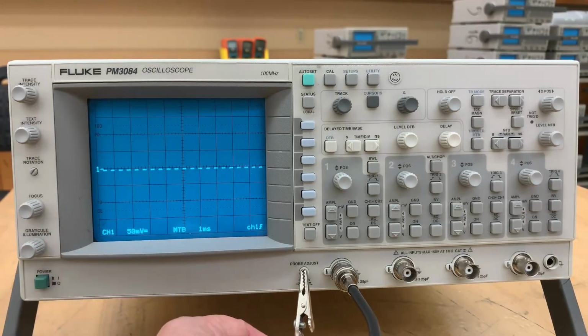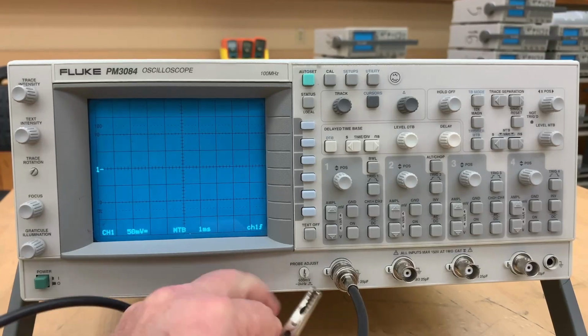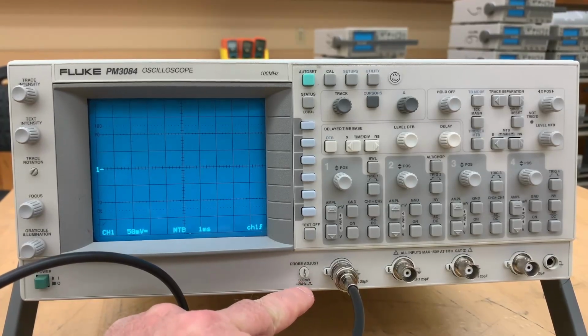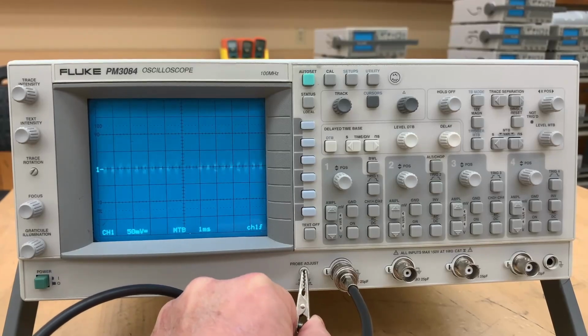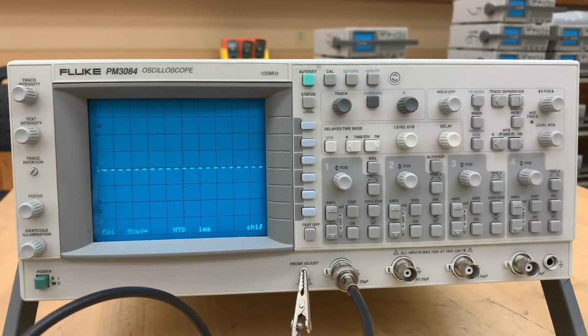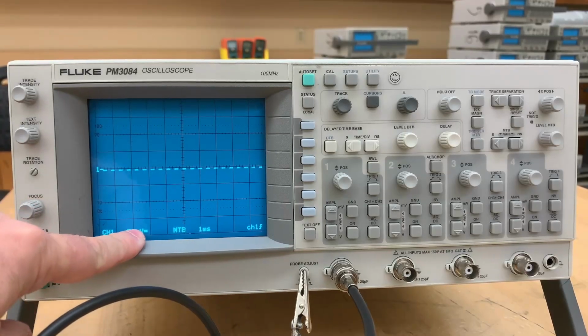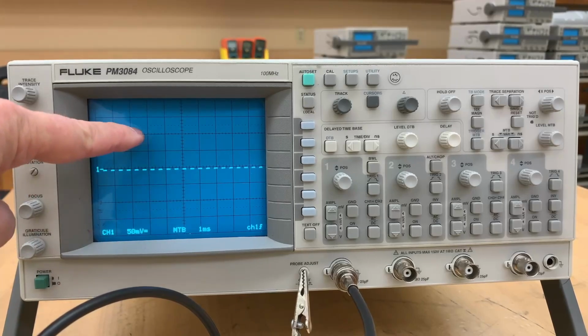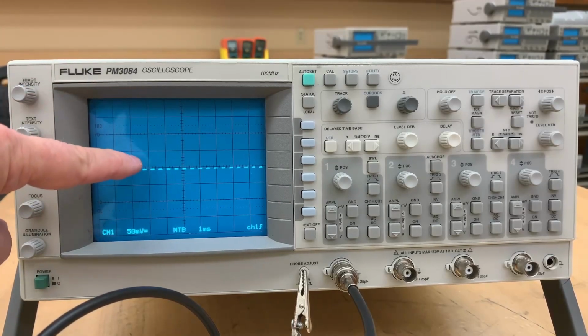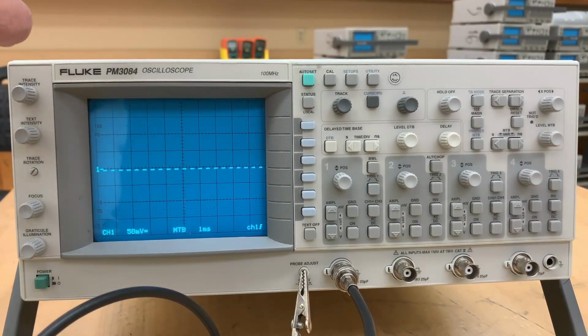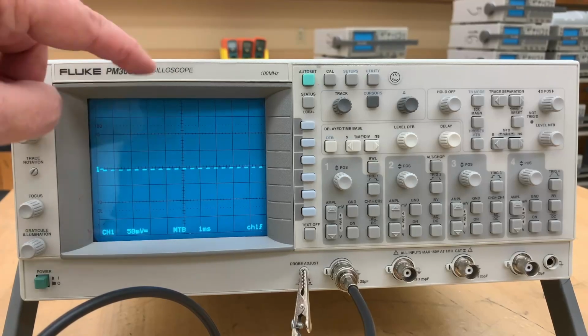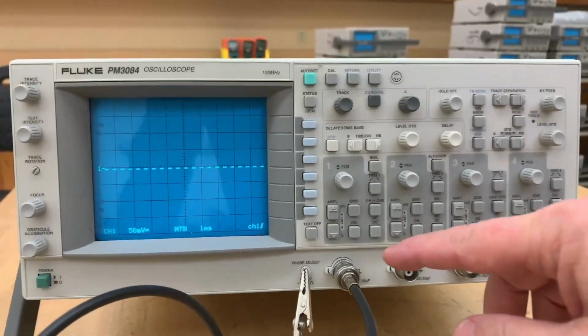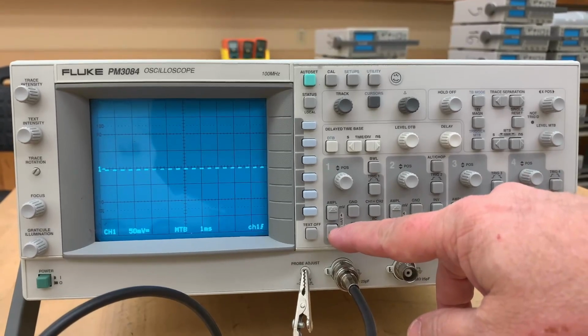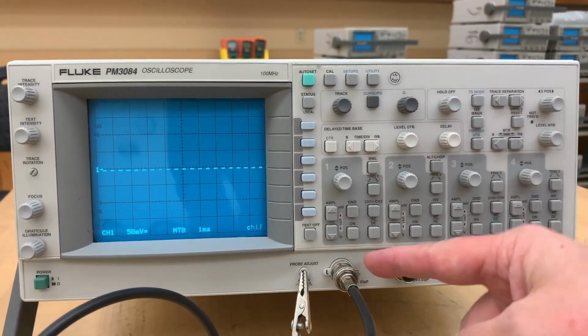Now, the probe adjust was saying it's 600 millivolts and 2 kilohertz, meaning that the peak of the signal should be 600 millivolts, and at the moment my setting is 50 millivolts, which means that each one of these things is 50 millivolts. So in this scale, 600 millivolts would be way out of the range. So therefore, what I need to do is adjust the amplitude of channel 1. So we're on channel 1.